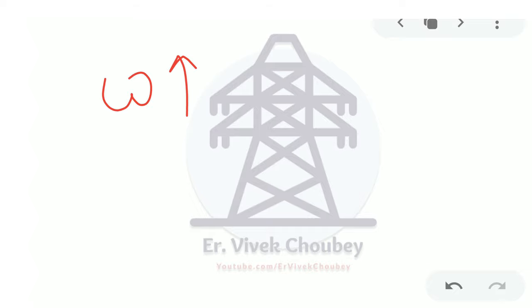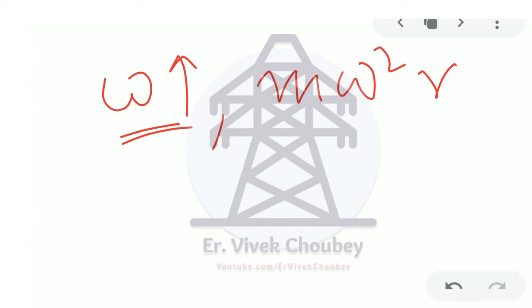As there is a rise in omega because of the sudden acceleration of the turbo generator system, there will be a rise in the centrifugal forces acting upon the generator as well as the turbine. Keep in mind that this is the increase in angular velocity, whereas the increase in centrifugal force is directly proportional to the square of the angular velocity. That means a huge amount of centrifugal force will act on the generator, resulting in wear and tear of the entire generator system. The conductors will be worn and torn, the bolts will come out, and there will be mechanical damage everywhere.